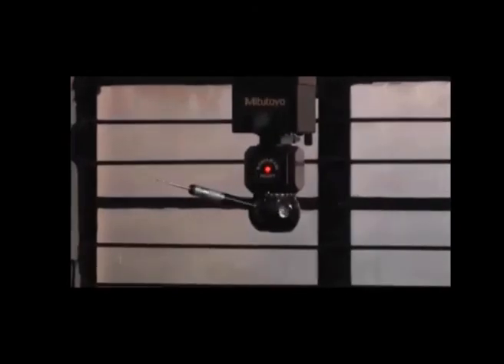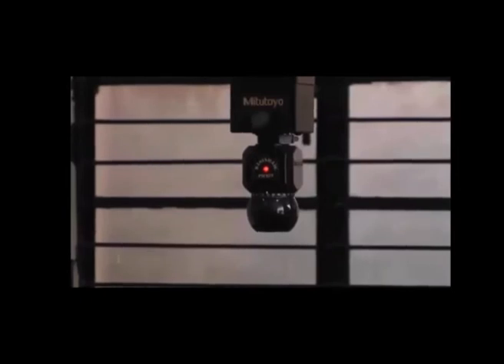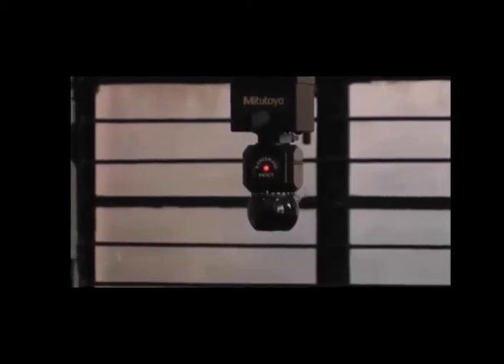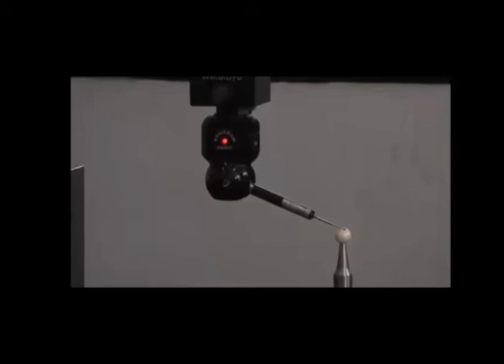Now, in this demonstration, we can see the movement of the probe. Now it is moving in B axis plus or minus 180 degrees, plus minus 180 degree movement. Now it is A axis movement. Now we can see the calibration of the probe using a master ball. Before using the probe, we should calibrate.